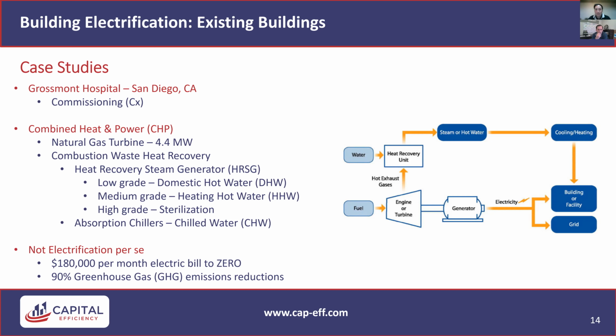Basically it was heat recovery. The combustion from that natural gas turbine was recovered to create steam in what they called an HRSG, or heat recovery steam generator. That created three forms of steam—low, medium, and high grade—that each served various purposes: domestic hot water, heating hot water, and sterilization of medical equipment. It might seem counterintuitive, but you can actually generate chilled water from heating using an absorption chiller, which was used in that practice.